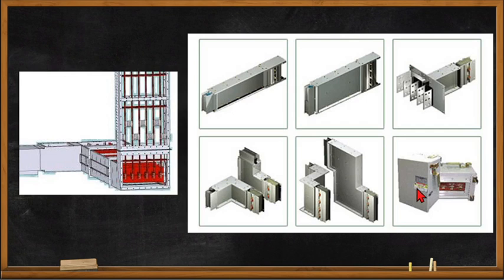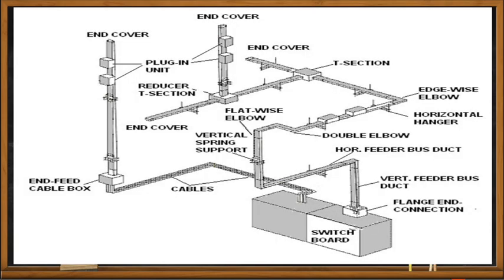This is an assembly of a busway showing its components: the feeders, the flange end, elbows (including a double elbow), and the power box or circuit breaker box attached to the feeder. This is a complete run of a busway system. Starting from the main switchboard or main distribution board, we have the flange end connection, vertical and horizontal feeders supported by a vertical spring support.